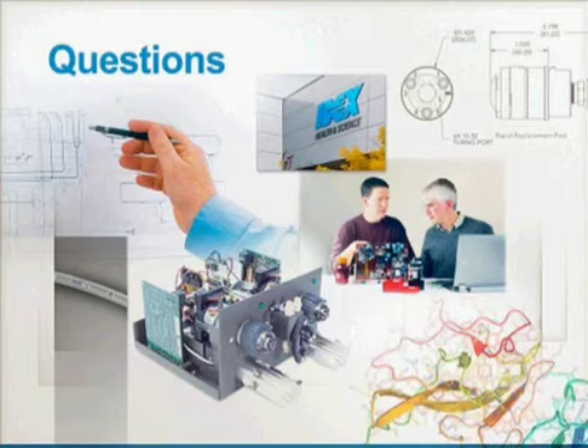So we have been able to do much more effective mid to modest pressure range flow feedback with piston pumps that are the Sapphire engineering pumps that we developed, and couple that into systems in some ways a whole lot easier than using the full stroke of the syringe without that flow feedback. So we feel that there's advantages to that. The pumps themselves have a stationary seal and have quite long life, so there's a little less maintenance involved since there's an awful lot of spaghetti typically in these LC-MS systems. Reducing that complexity sometimes helps as well. Any other comments from you, Darren, on this one, on the syringe versus piston?